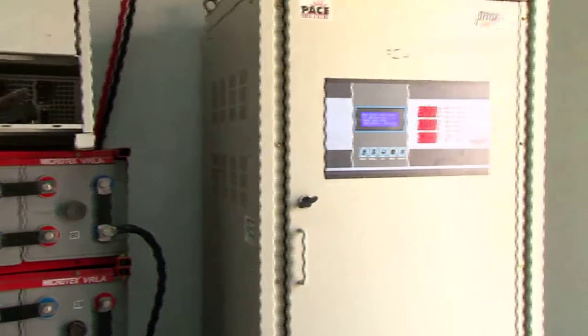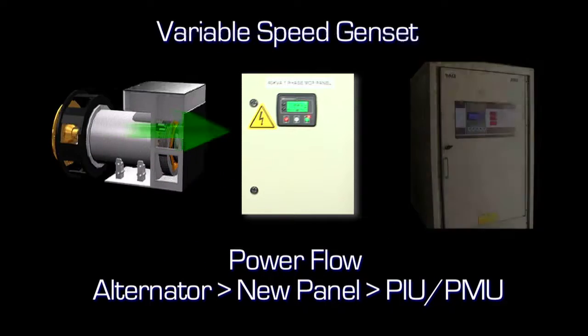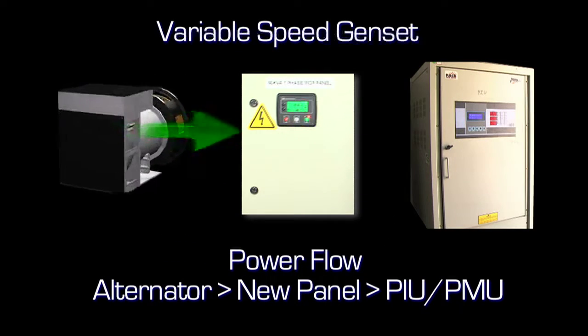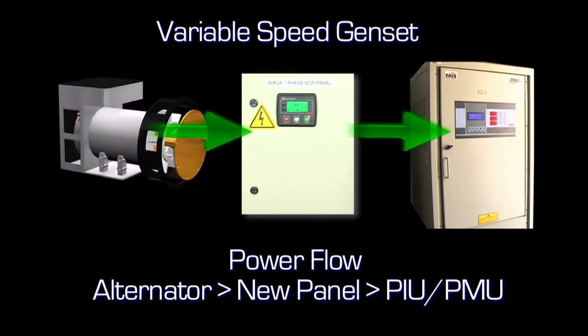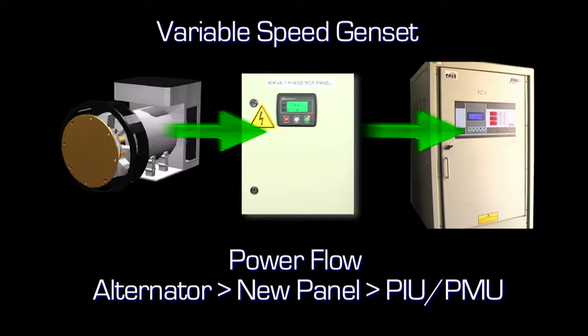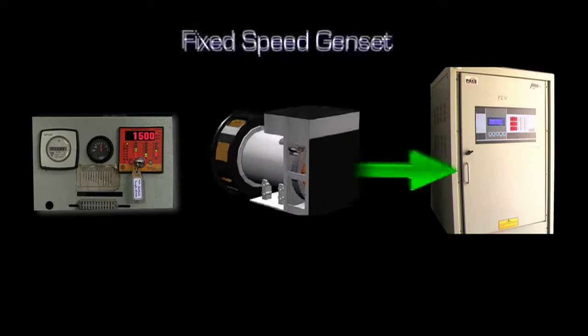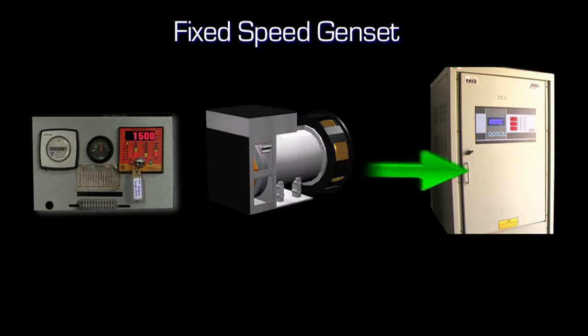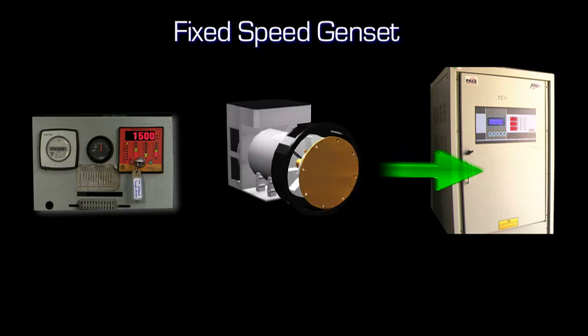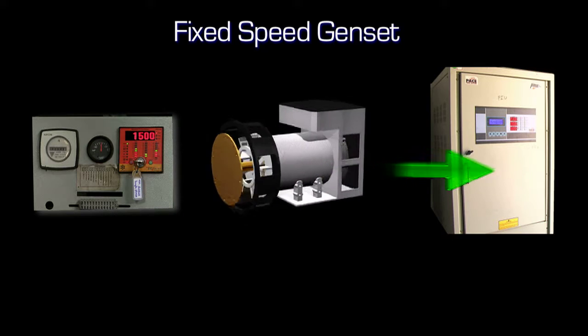The only difference as far as the PIU, PMU connections are concerned is that in case of the variable speed genset, the genset alternator's power flows into the new control panel and from there it flows towards the PIU, PMU. In case of old control panels, the PIU PMU sometimes receives electrical power straight from the genset alternators.